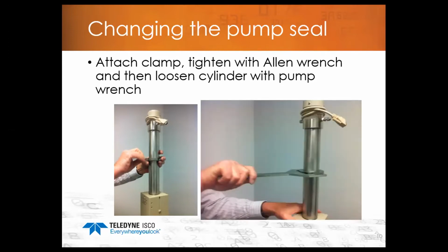And here's a photo of the cylinder clamp on the cylinder, and then in the wrench package we have the mating wrench that fits onto the clamp, and then with that wrench and clamp you can unscrew the cylinder. Now most times if you don't have that, you can unscrew it by hand, but there are occasions where over time that cylinder can get kind of tight in that mounting block, and sometimes you have to have the wrench package, or some customers have used a strap wrench, and we have had pretty good luck with customers that have used a strap wrench to remove the cylinder.